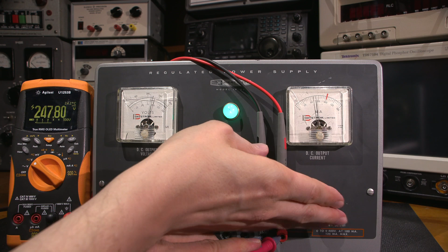And that's the C output. We're going to have to test that too. Bring it up to 100 mils, so that's the max it's supposed to go to, right on the red line. So 374 - we'll say 374 right now, and 100 mils of load. Not bad, that's right at the max. About 2 volt drop - well, a volt and a bit anyway.